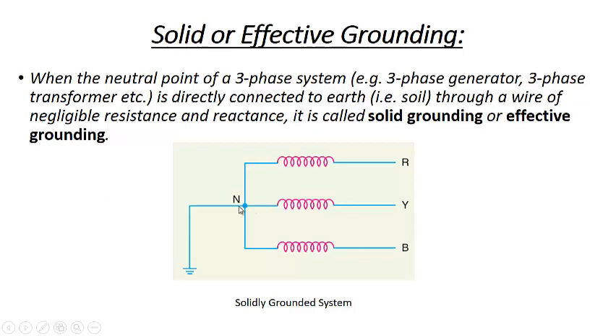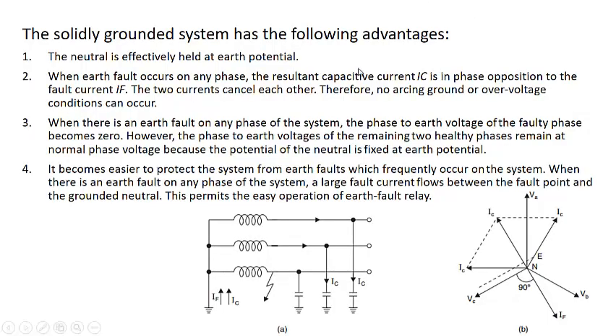So this is how a neutral is connected directly to the ground through a wire whose resistance or reactance is very negligible or close to zero. Now what are the advantages of this? The neutral is effectively held at the earth potential. In the previous case, when a fault occurs, the neutral comes to the potential of the phase C. But in this case, it will be held at the earth potential. When the earth fault occurs on any phase, the resultant capacitive current is in phase opposition to the fault current. You can see that here. Earlier, this is IC. VA and VB will remain at their own voltages because now this neutral is not changed. Neutral voltage will remain at zero voltage.